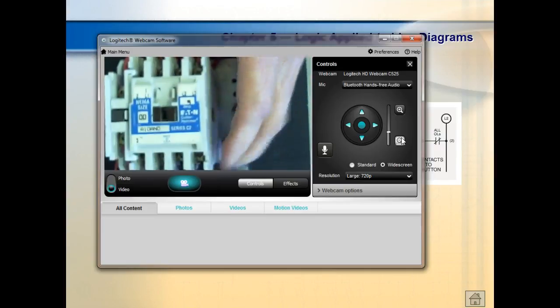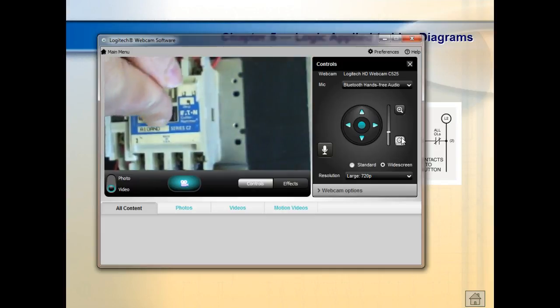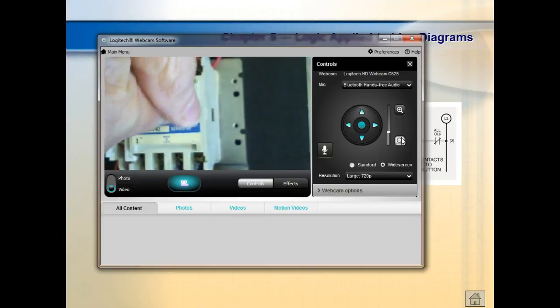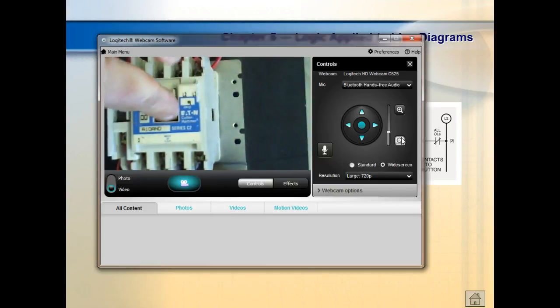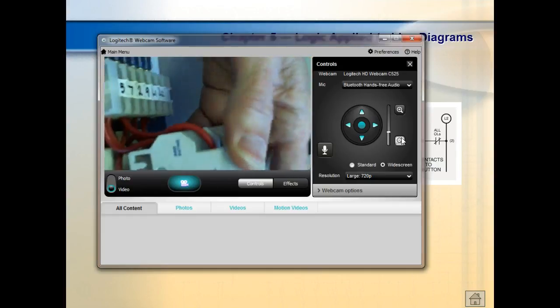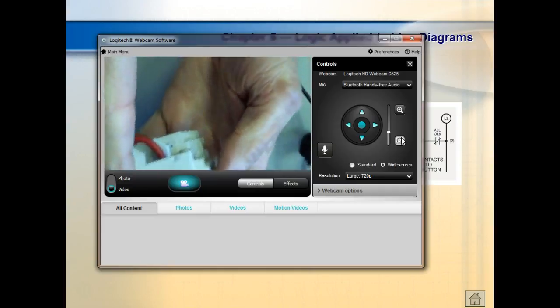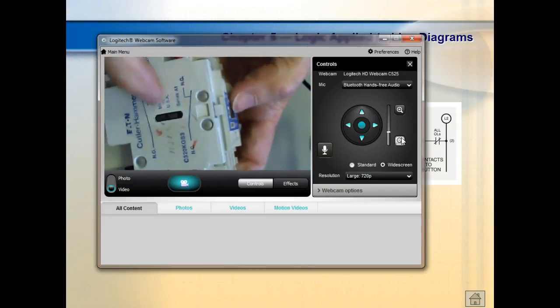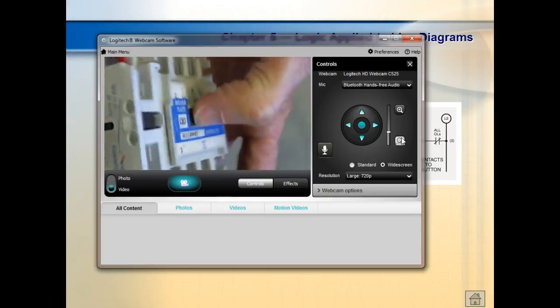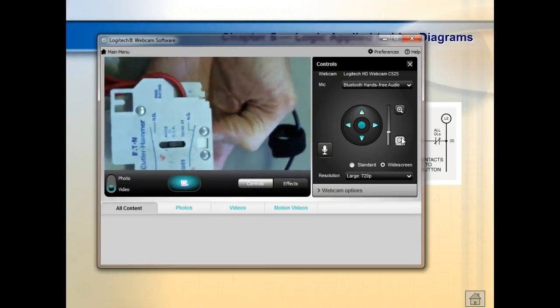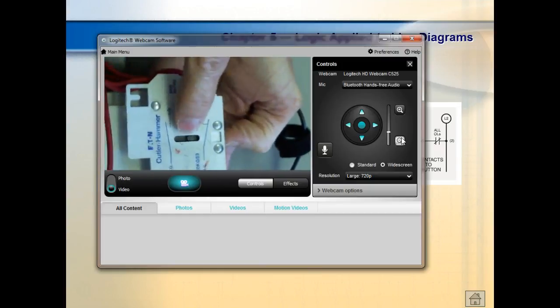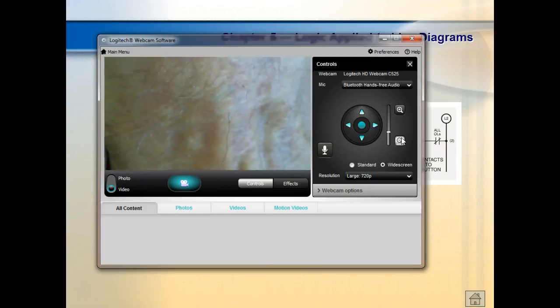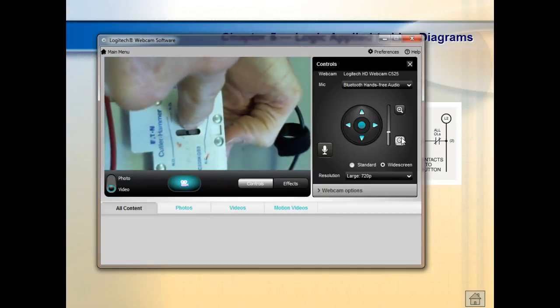So, by the way, most of your relays have what we call an override or manual operator or push to test. Be real careful when you do this. This could kill people. So know the effect of what's going to happen when you force this contact. Can you see me forcing it? Now, what happens if you see this auxiliary contact, normally these are screws. They've got this braided on here. But notice you can actually see the operator operate on the side. I don't know if y'all can. If I pass it around, you can. It's the same color. Can y'all see it move? So that means I could take another auxiliary contact and put it on here, and it would operate off this thing right here.